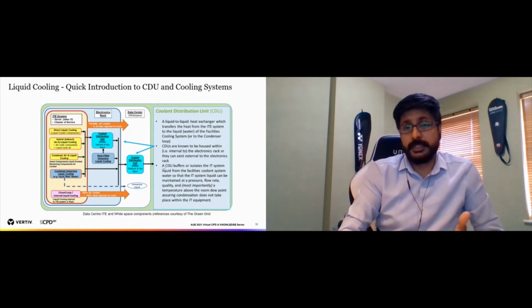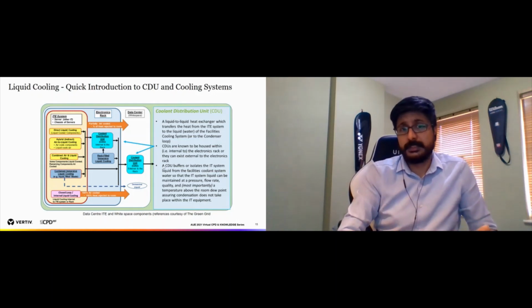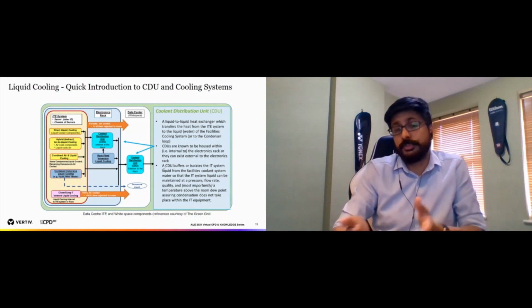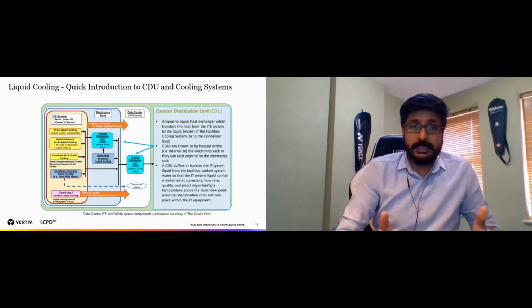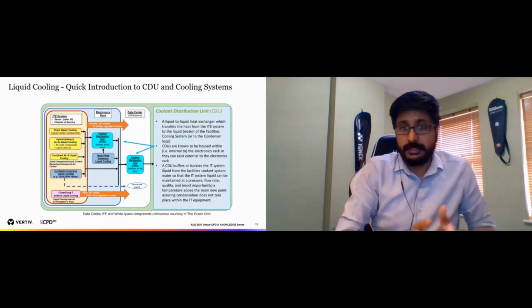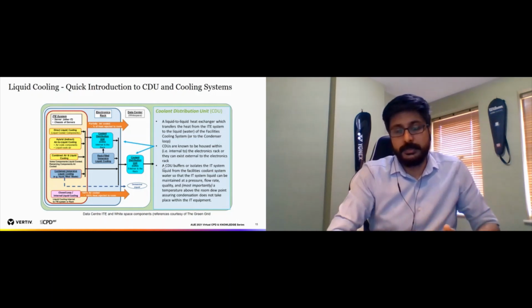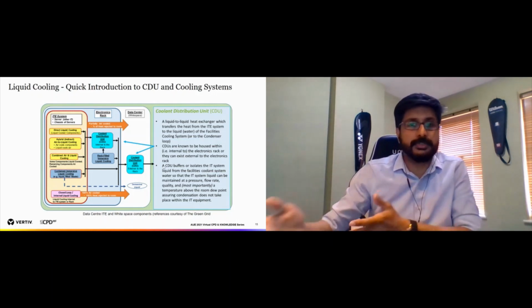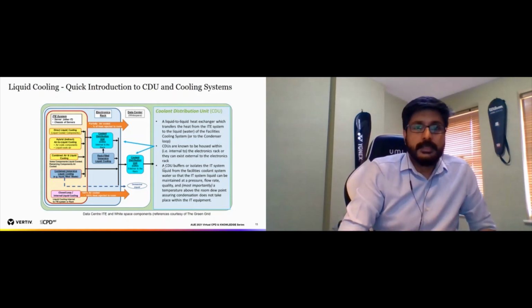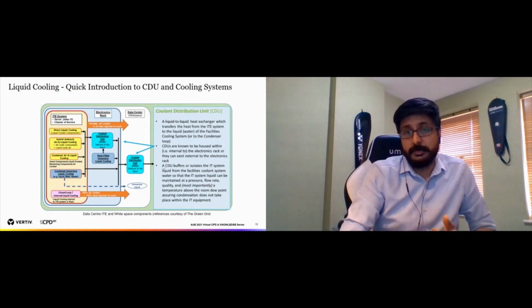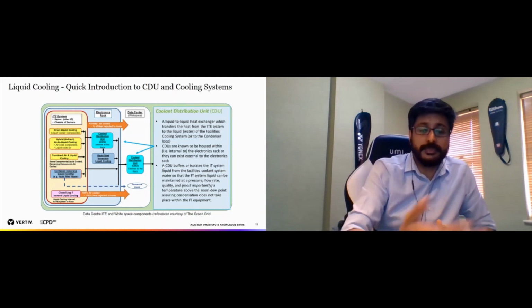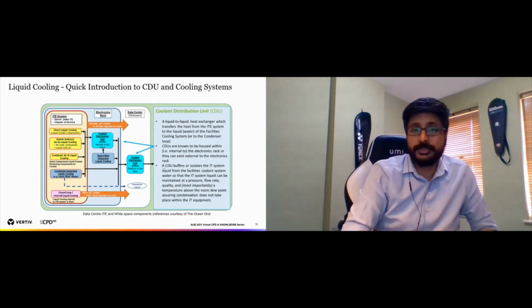The immersion cooling option can be either fully contained inside the rack, or, like the chip cooling, you can have a cooling distribution unit sitting outside. This has a heat exchange system, a heat exchanger, in there, so the facilities liquid and the external liquid are never mixed. The other advantage of having a cooling distribution unit is that it maintains the temperature within the server rooms or the facilities rooms higher than the dew point temperature. That means there are no condensation issues as well.